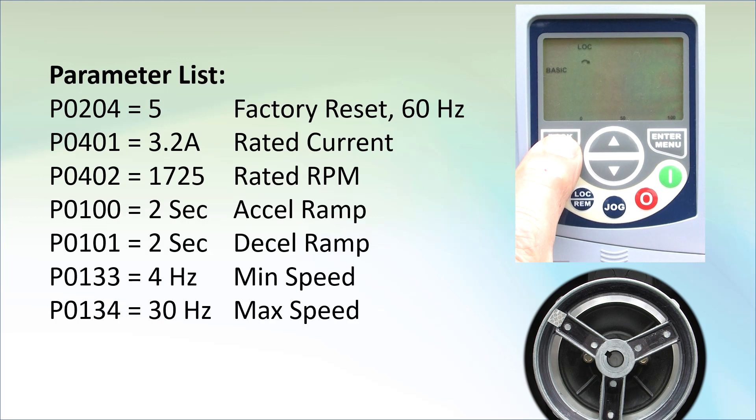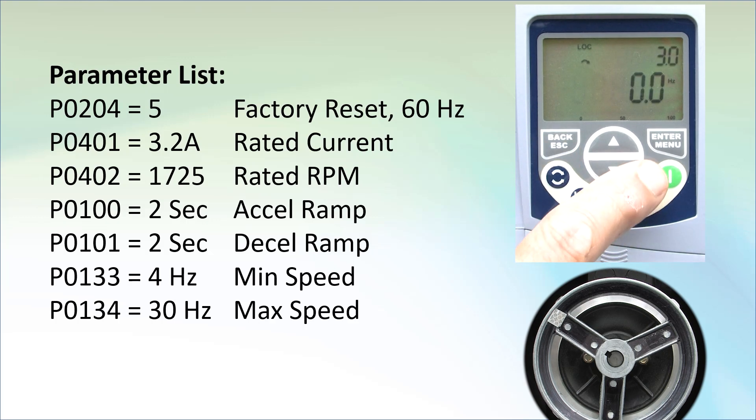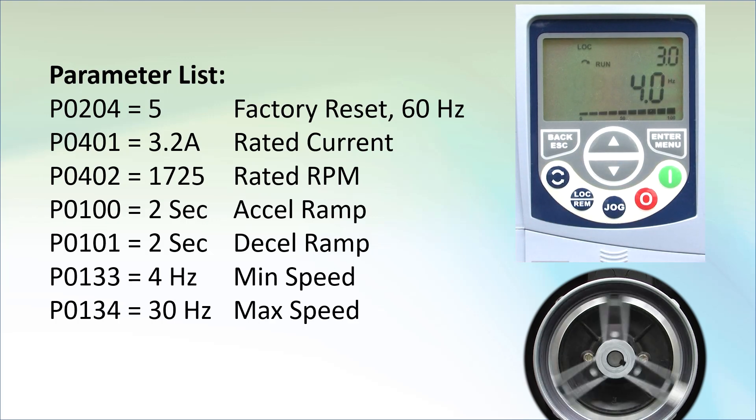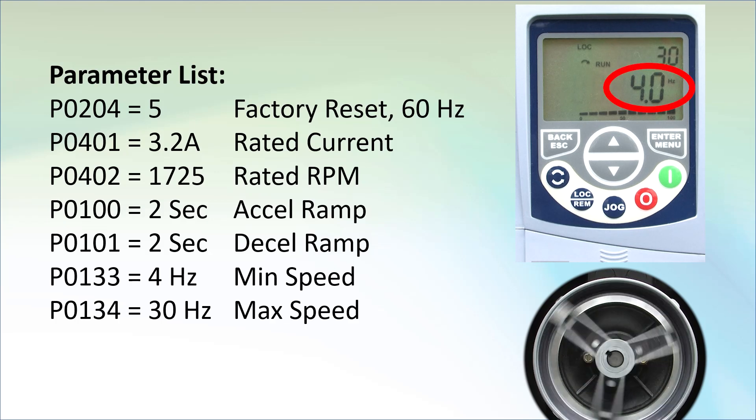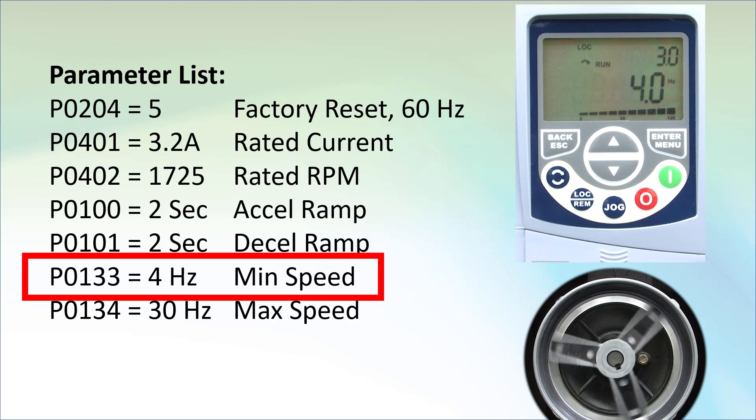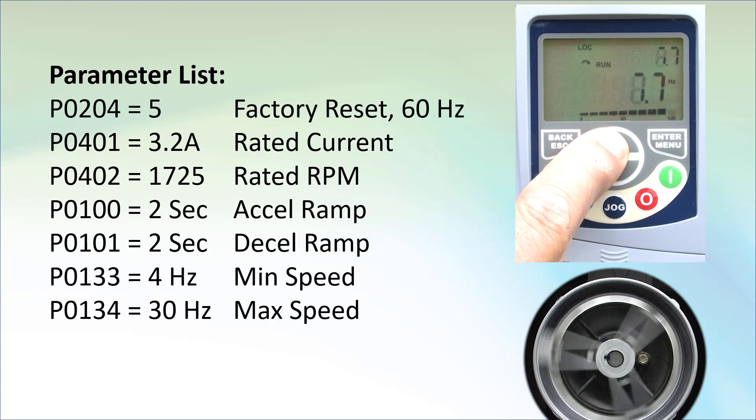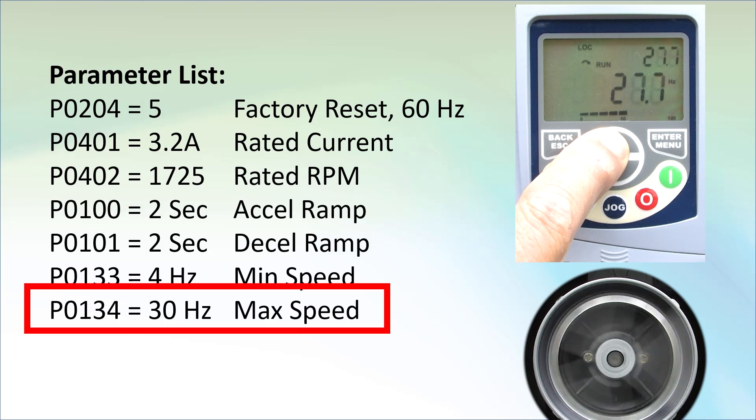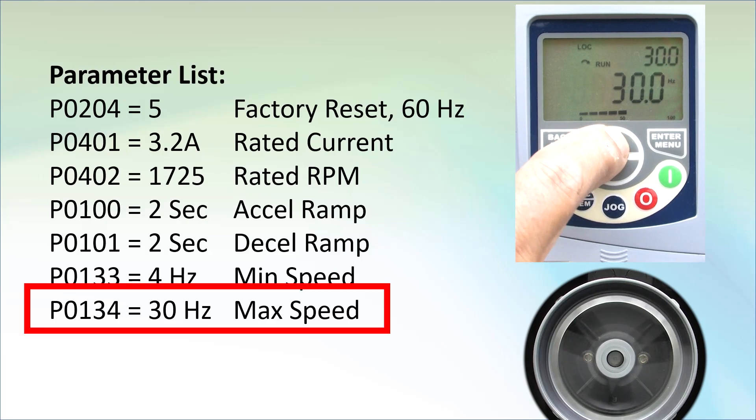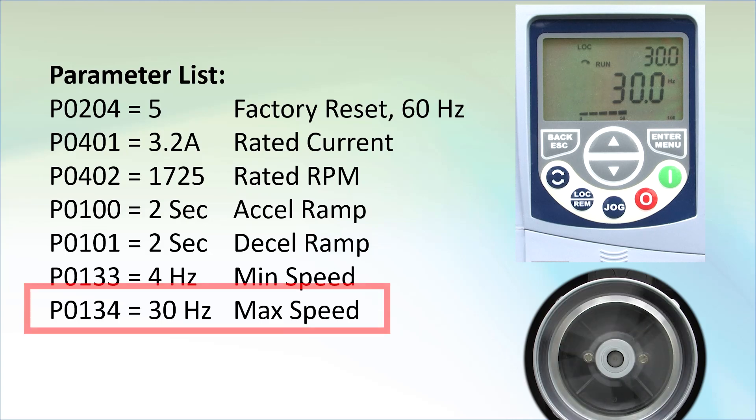Press escape twice to get back up to the top level. Hit the run key and sure enough the drive ramps the motor to the 4 hertz minimum output frequency we just entered. Perfect. If I press the up arrow to increase the output frequency, then the motor responds accordingly. Of course since we set the max frequency to 30 hertz, the drive won't let us go past that. Exactly what we expect.